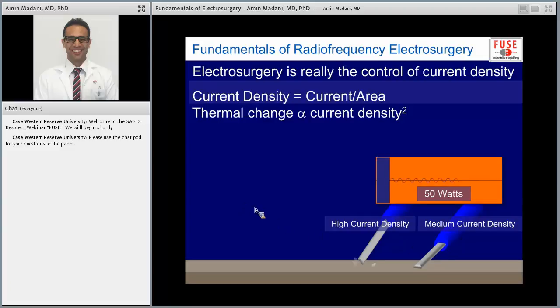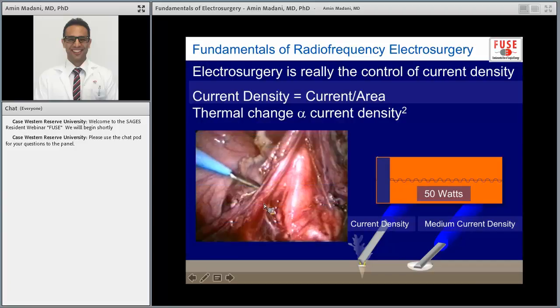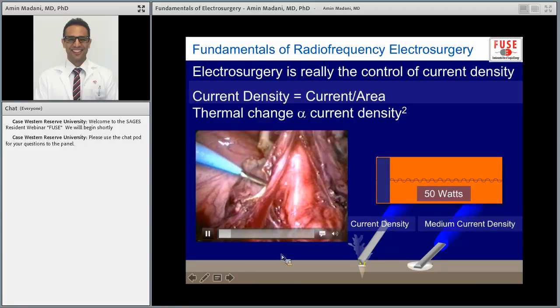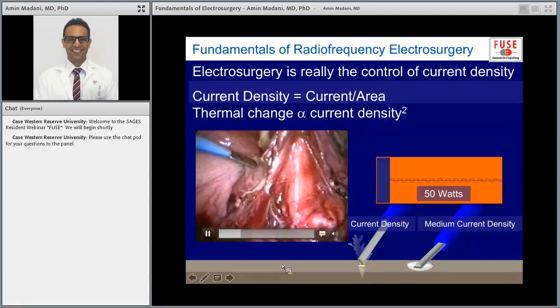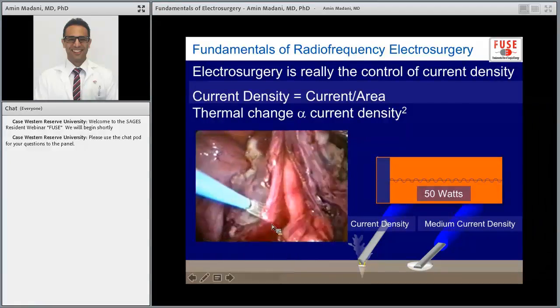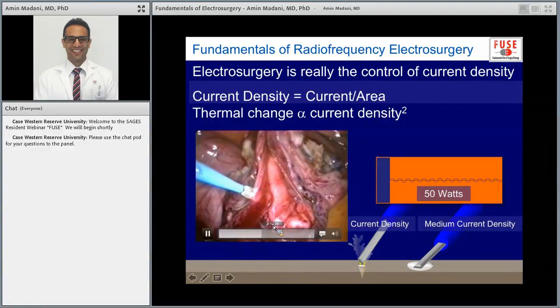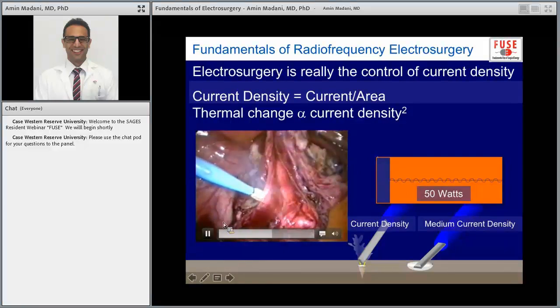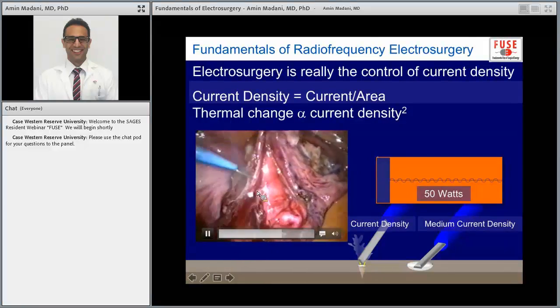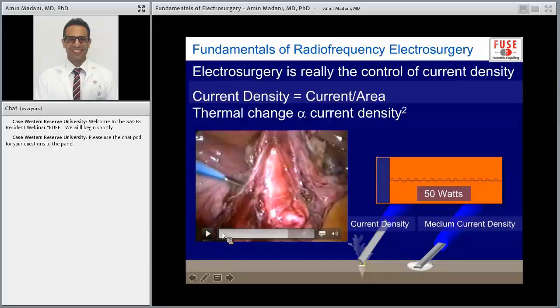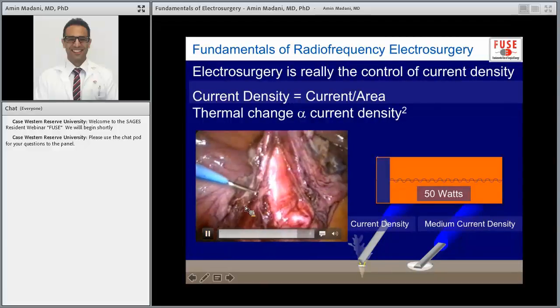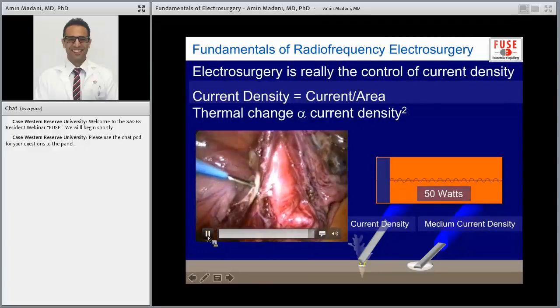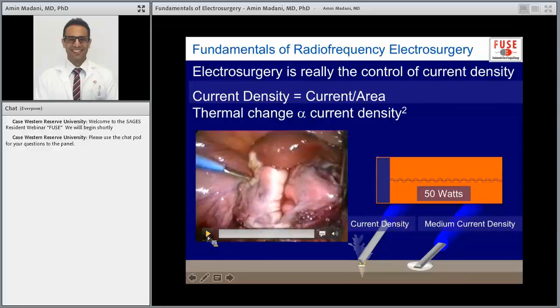So this video really shows it nicely. In this case, they're going to use the flat part of the electrode, and it's going to be lower current density. So it's going to raise the temperature of the cells to the 60 to 95 degrees Celsius range, enough to desiccate the tissue. It hasn't vaporized it yet because it's lower current density. But when you start using the tip, all of a sudden the thermal effect is higher, and because the thermal effect is higher, it raises it to above 100 degrees Celsius, where you also get vaporization and more of a cutting effect.